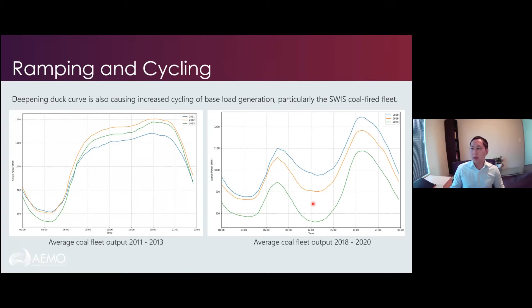But just a bit of perspective here, the ramping situation in the SWIS is nowhere near as bad as what's happening in California. So we're talking about 134% from the trough. California's got like 600%, 6 times the amount of ramping required at the trough. So by way of mitigations, what we're doing is we're just making sure that on these high ramp days we have the flexible generating plant online. So this is mainly gas turbines and they're not on outage. We have enough ramping capability. And we're now doing some additional work on the capability of the fleet to meet ramps.